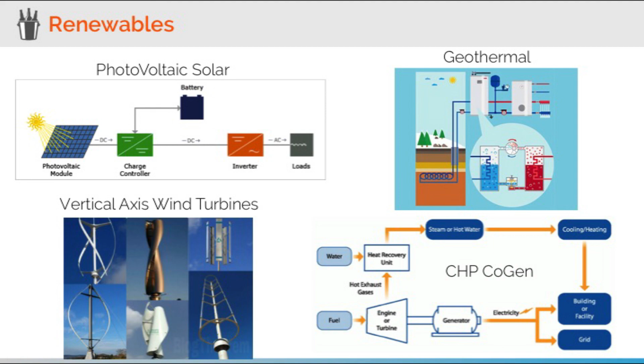We'll talk briefly about on-site cogeneration, as it's a growing topic of discussion among large public and private organizations. CHP, also known as combined heat and power, typically uses gas to fire a turbine, which turns a generator to create electricity, and captures the exhaust or hot gases for useful thermal energy. It can be used for process heating or cooling, or comfort heating or cooling. The takeaway is that while it's not renewable, it can be a great source of baseload power—the power needed to run your facility when you're closed or have little operations.